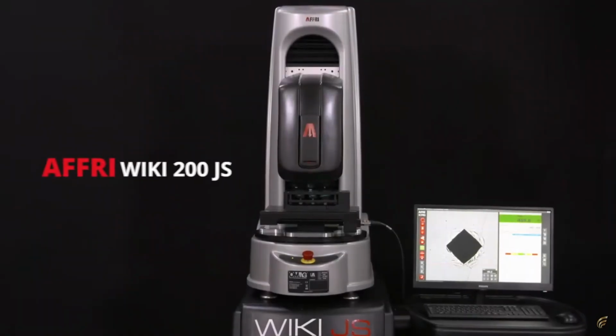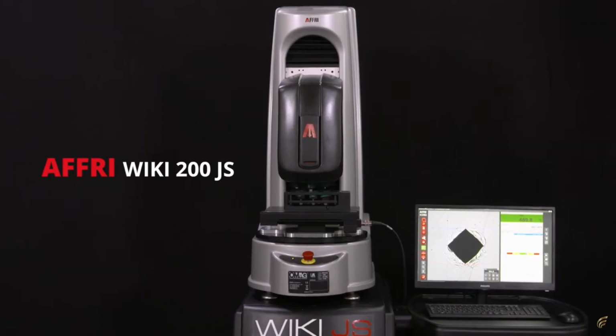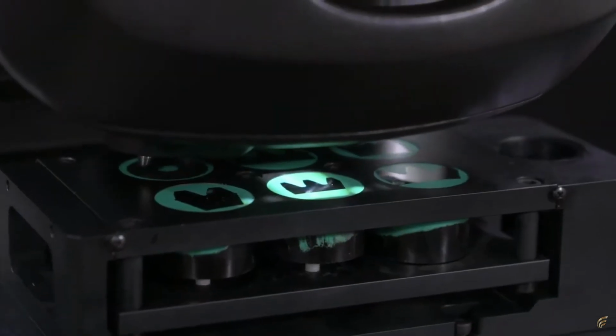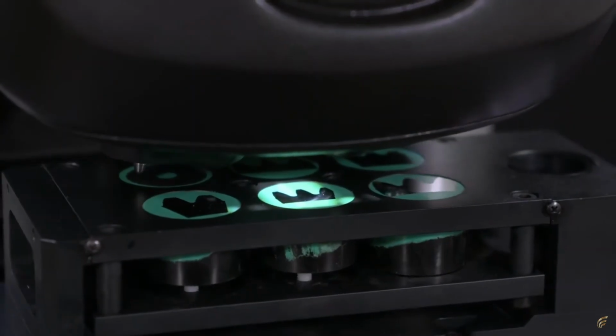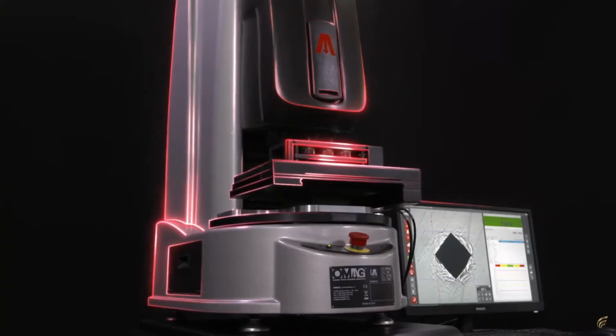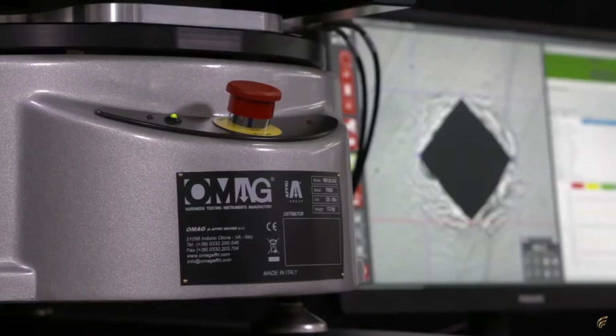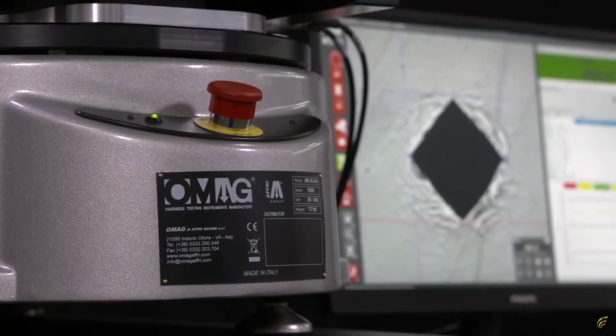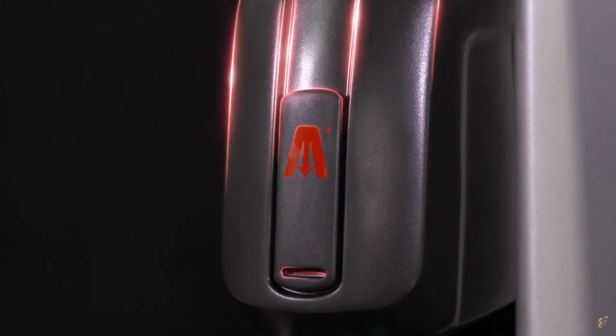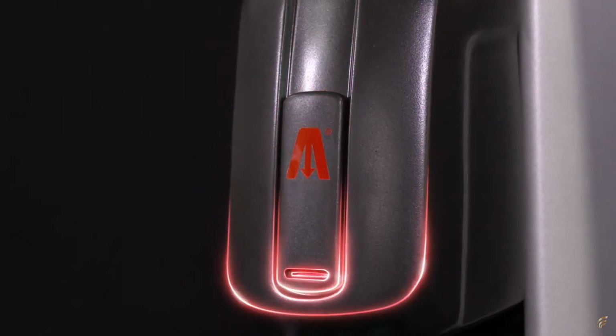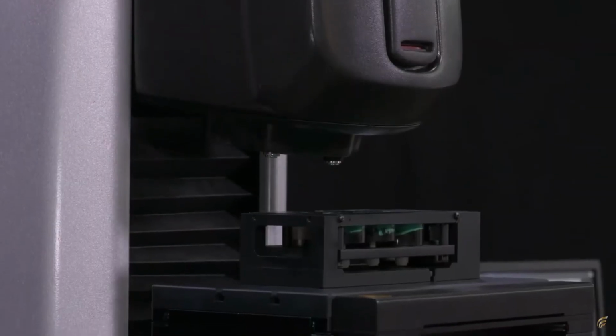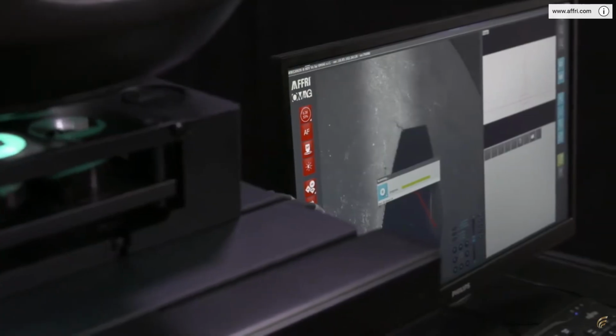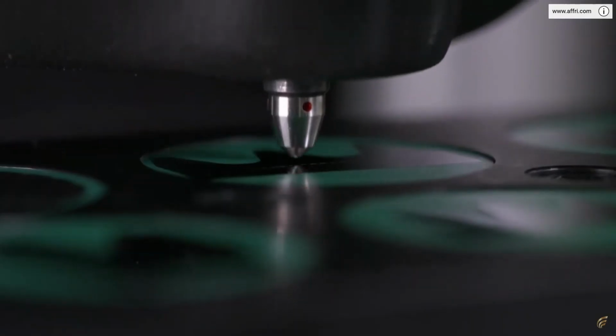The AFFRI Wiki 200JS is a totally automated, extremely accurate system for micro and macro Vickers and Knoop hardness testing in compliance with ASTM and ISO international standards. The motorized hardness tester is used for the automatic measurement of CHD for carburizing, nitriding and surface heat treatments.